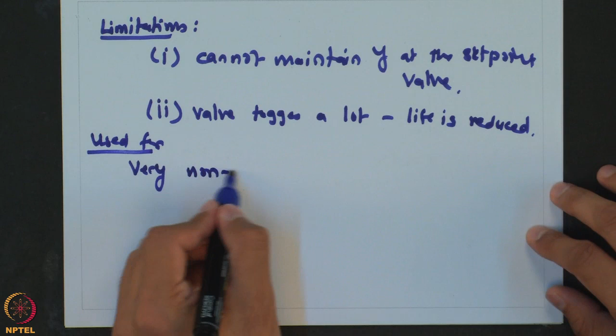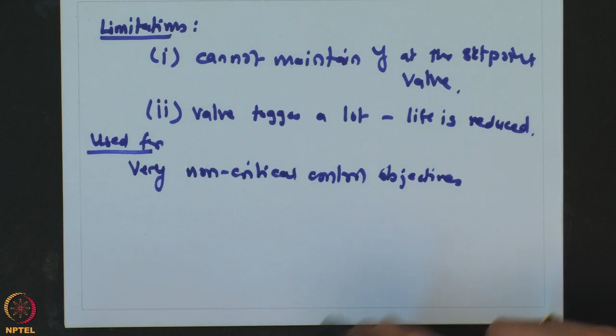very non-critical control objectives, where a significantly large deadband will be used to avoid the valve toggling, and you are still okay by having that much of an offset. So, one of the examples from real life is level control in intercooler for air compressor.